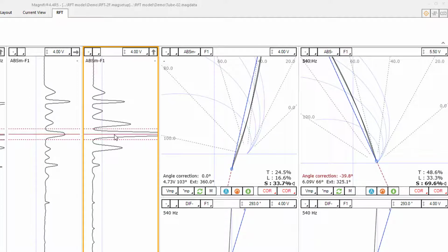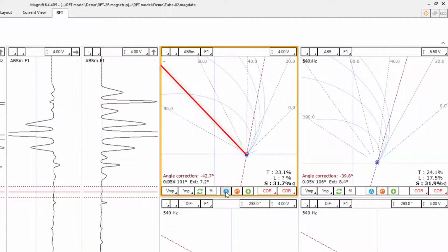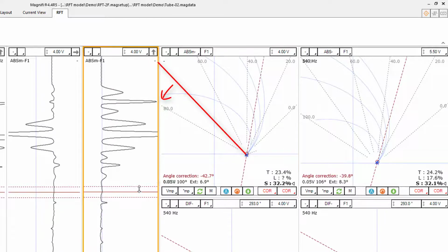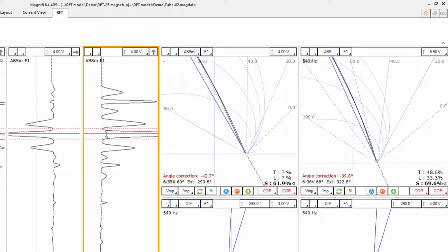If I do the same with the theoretical model, I just bring it again in the nominal area and I normalize. And when I look at the signal, the accuracy is better. So the 40% is measured at 43.7%, but most importantly, the 60% remains very close at 61.8% compared to 69 here. It's a good improvement, and the accuracy is maintained between plus and minus 5%.